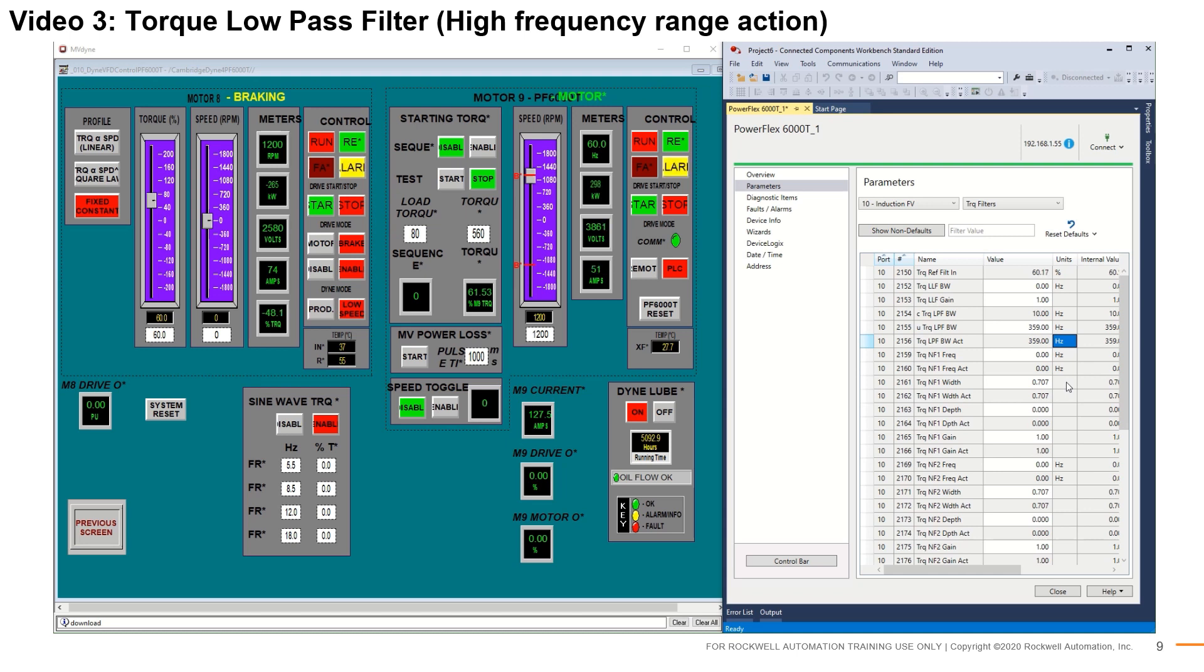Observe that with adaptive tuning turned off, all the torque reference filters are again set to their original configurations. Note parameter number 2156, the actual torque low-pass filter bandwidth, which now sits at 359 hertz. When the feature is enabled, the low-pass filter starts to detune and stops when the filter bandwidth matches the offending high-frequency component's value. Observe that when the high-frequency component is detected by adaptive tuning, the torque low-pass filter bandwidth decreases from the original 359 hertz to 20.2 hertz.